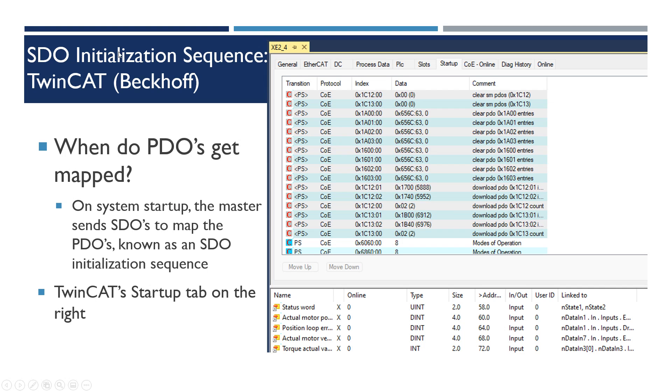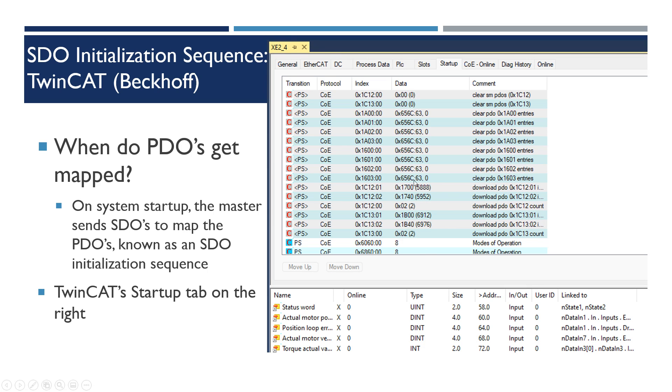An initialization sequence, this is what you'll typically see for most masters. They have a nice startup process that on startup the master can send these SDOs to map those user mappable PDOs. This is what TwinCAT looks like, this is Beckhoff. They invented EtherCAT and it's a very user-friendly IDE. The first thing to do is the sync manager 2 and 3, they set it to 0 and then it just disables it.